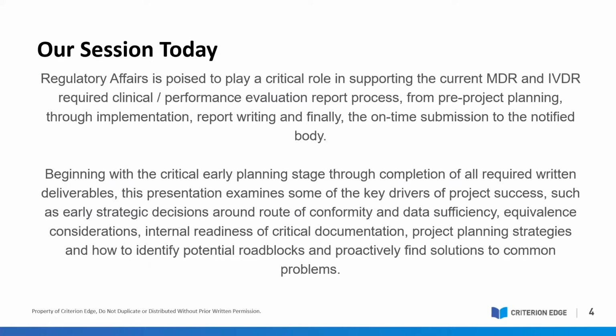Thanks for joining. We've received a lot of questions about the topic on the docket today, which is about how regulatory affairs can help shepherd along and support the clinical evaluation process. Regulatory affairs really is poised to play a critical role in supporting the current MDR and IVDR required clinical and performance evaluation report process. And that's from pre-planning all the way through implementation and writing, and then finally the on-time submission to the notified body, which is the end of the road for the submission part. And then the work starts again when the notified body will finally get back to you with their responses. So beginning with this early critical planning stage, through completion of all required written deliverables.